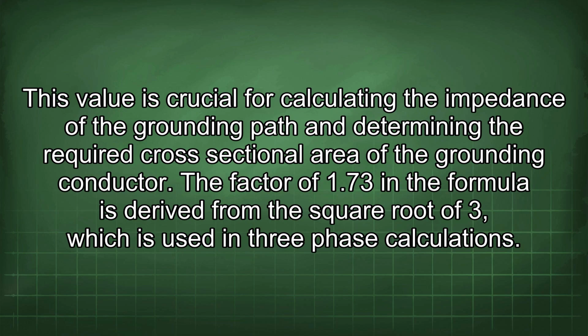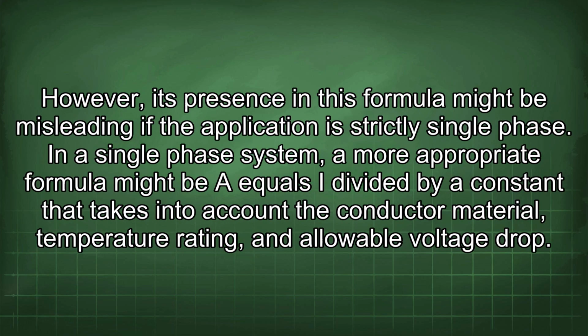The factor of 1.73 in the formula is derived from the square root of 3, which is used in three-phase calculations. However, its presence in this formula might be misleading if the application is strictly single-phase. In a single-phase system, a more appropriate formula might be A equals I divided by a constant that takes into account the conductor material, temperature rating, and allowable voltage drop.